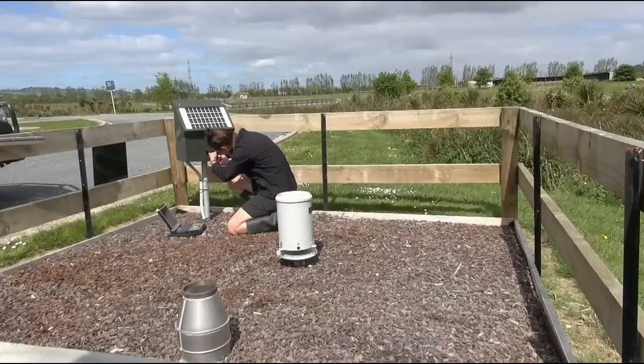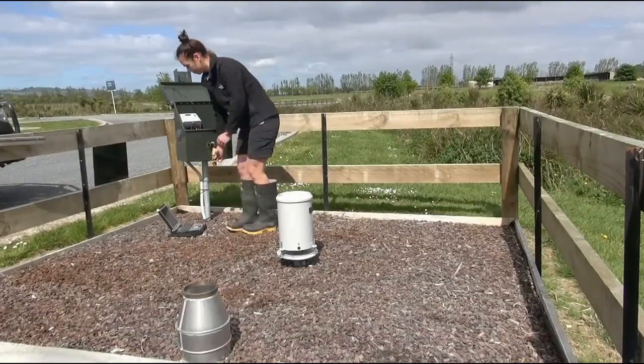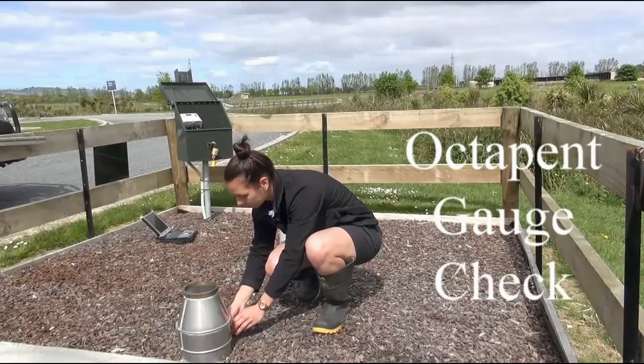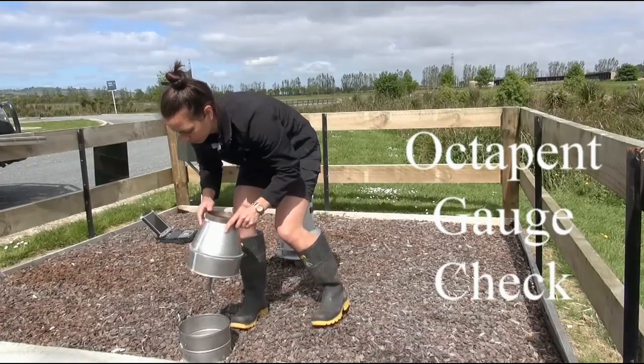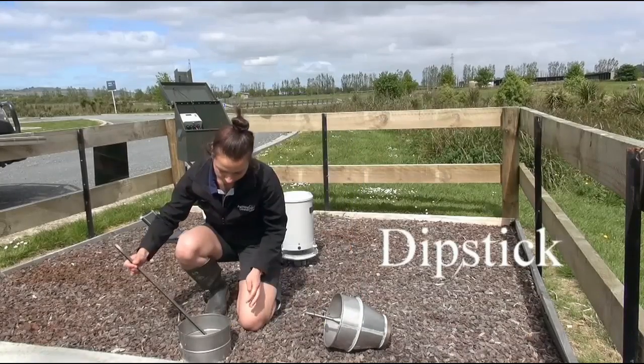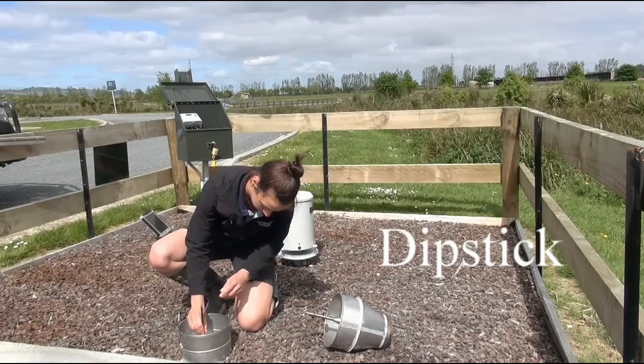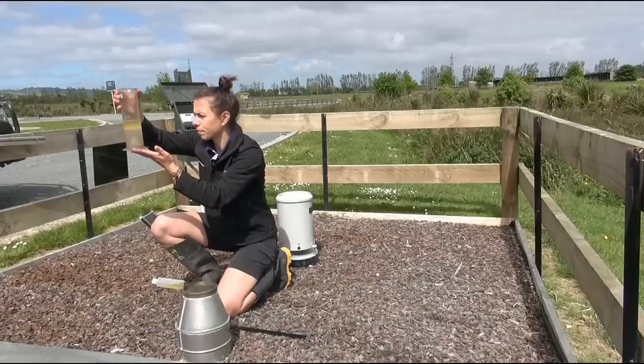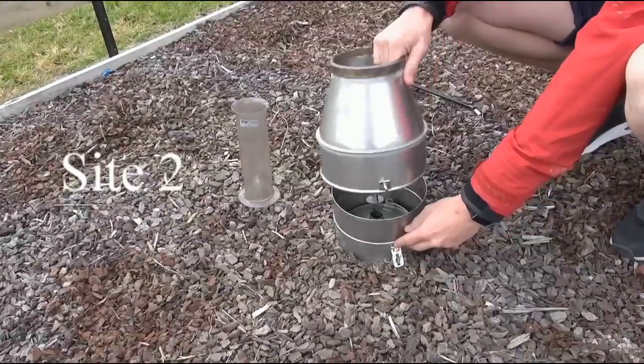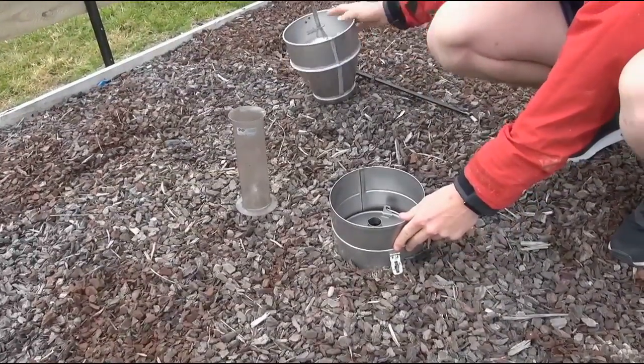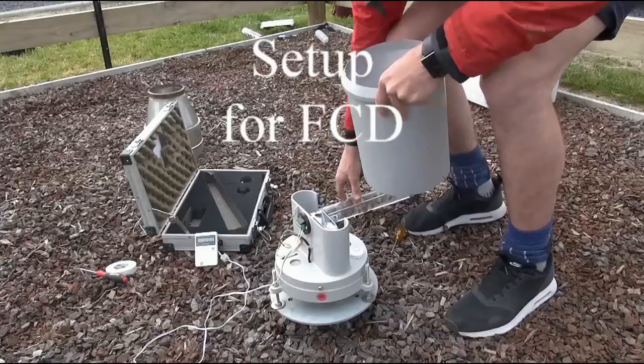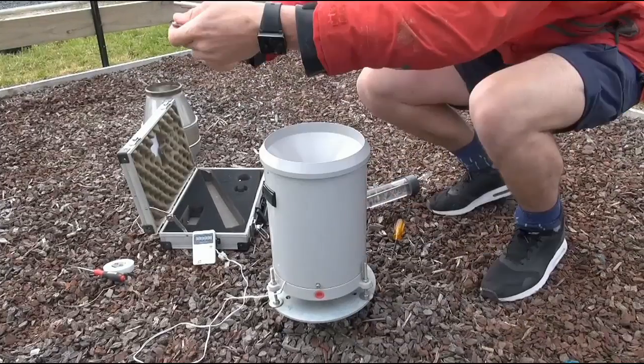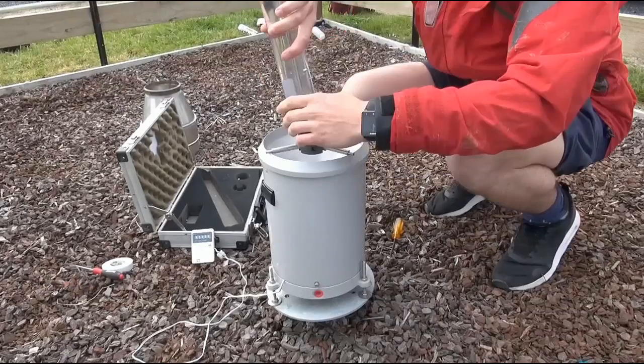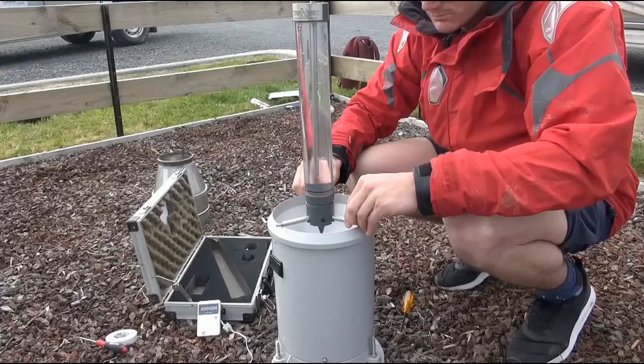So now we're going on to rain gauge. So this is a typical rain gauge enclosure, fairly new one by the look of it, and how things are inspected, how the check gauges check the dipstick and volumetric flask. Remember, this is a shortened version of what's actually shown, but just how to do checks and setups and calibration of the gear in the field.